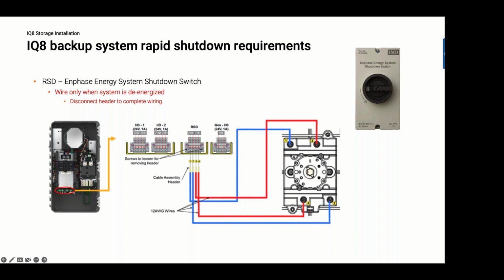Now, the way that this switch gets wired, this is the best practice again, is that you have to be really careful about how you wire this, because this switch gets wired into the RSD, or rapid shutdown device, port of the system controller 2. You have to wire this exactly, and you have to wire this correctly. One thing I will say about this, critically important, please take note of this, is that you should never wire this switch when the system is hot, all right?